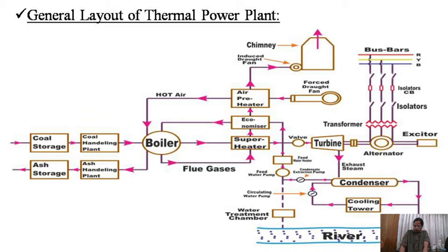The superheater consists of a group of tubes made up of special alloy steel. These tubes are heated by the heat of the flue gases during their journey from the furnace to the chimney. The heated tubes convert the wet steam into dry steam. The superheater increases the overall efficiency of the plant. It also avoids the corrosion of the turbine blade.